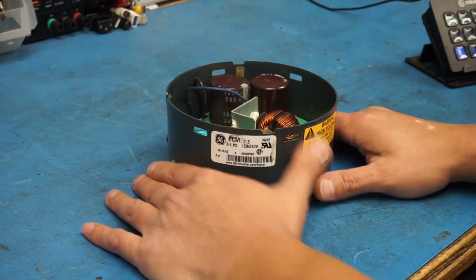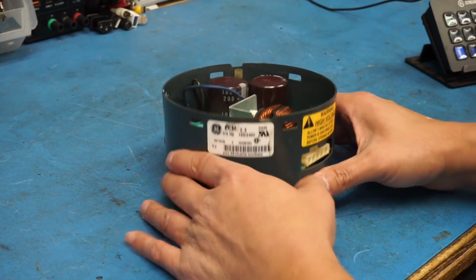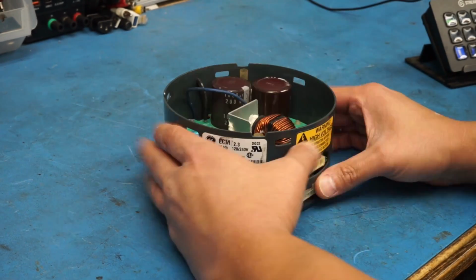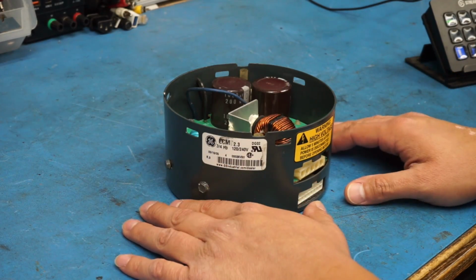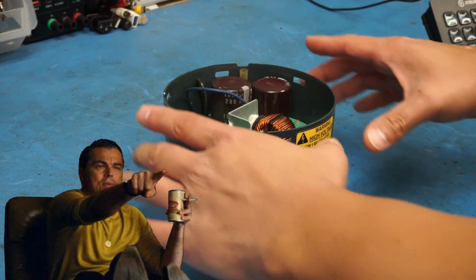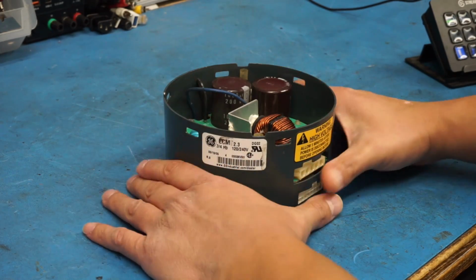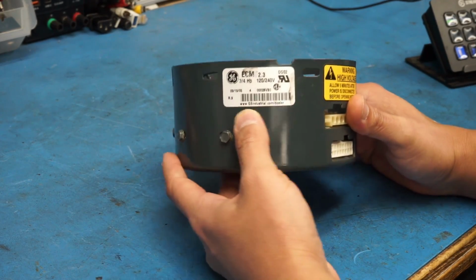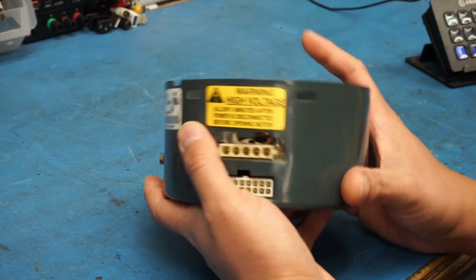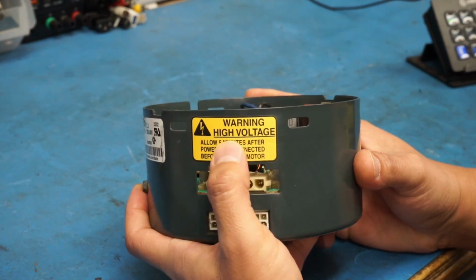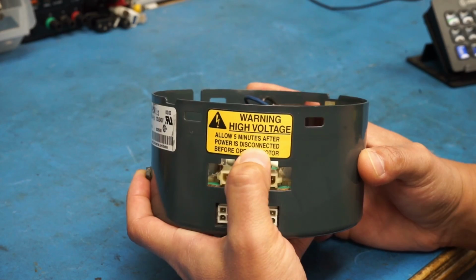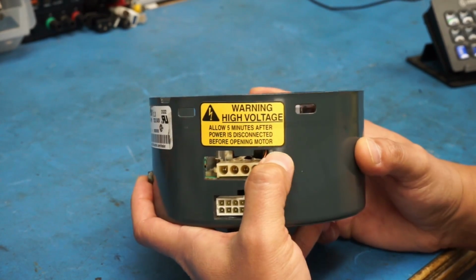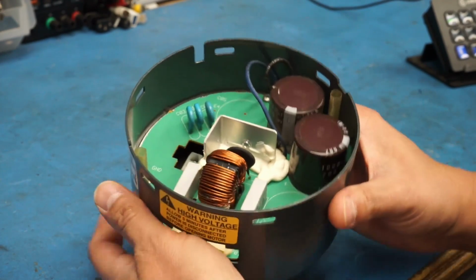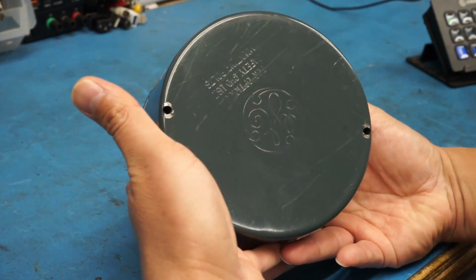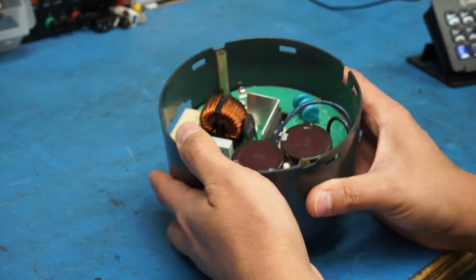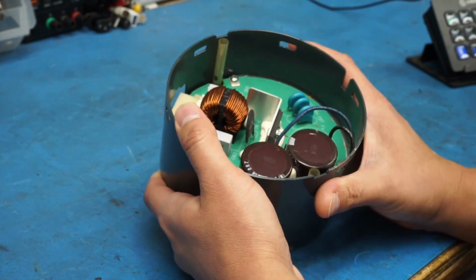I can already hear some people asking, what's a DG02 ECM 2.3? Any HVAC people out there are probably like, oh, I know exactly what that is. Honestly, I wouldn't have known either if I hadn't pulled it out of the equipment it was installed in. But if we look at this label right here, above these connectors, it says warning, high voltage, allow 5 minutes after power is disconnected before opening motor. So that's our big clue. There's no shaft sticking out of this, so it's obviously not a motor itself. So what this actually is, is a motor controller.